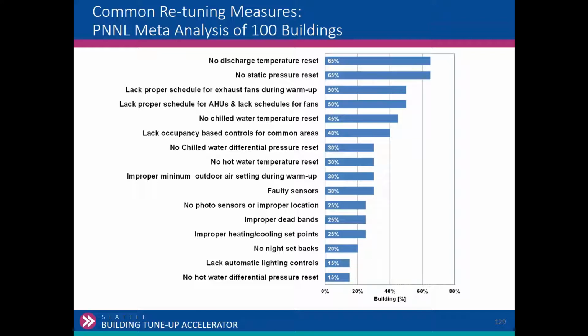In terms of the measures, PNNL did this analysis of 100 buildings. Where were the savings opportunities in these larger buildings with BAS systems? Discharge temperature reset. It may have the capability of resetting 5 degrees, from 55 to 60 or whatever that is, but for whatever reason, they've abandoned that strategy. There's a variety of reasons why, but verify whether they have the capability of doing that and whether they are employing that strategy. Same thing on static pressure reset, with static pressure set points set too high. Has anybody seen a duct static pressure set point higher than it needs to be? Is there an opportunity to reduce that?